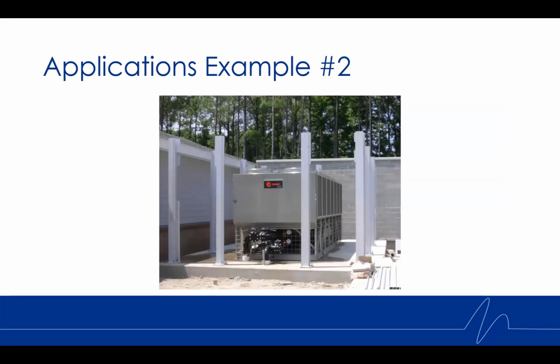Here's a second example. So this was a chiller at a school. Again, a lot of these applications end up being retrofit. The majority of the projects we do, the noise control is not planned ahead of time, and it ends up being a retrofit solution because the noise was not taken into account early on. So this is a chiller. The picture that you're seeing here was basically taken from the sidewalk. In this case, we did provide the structural steel and the structural engineering for those posts. So this is with the posts installed.